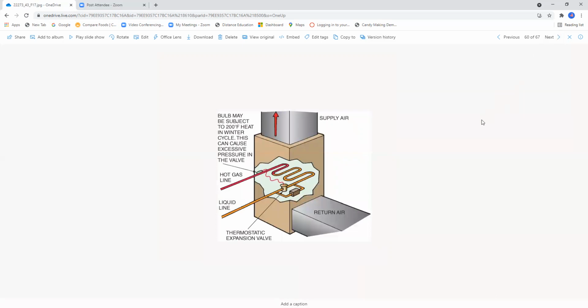Okay, here we have a bulb, and this is something we haven't really talked about. Let me find the illustration in the book, make sure that we get the correct information regarding this. Okay, this is going to be found on page 1282, under figure 43.17. This illustration shows that care must be taken in the choice of a TXV. If an ordinary TXV sensing bulb were to be mounted on this gas line, it would get hot enough to rupture the valve diaphragm. So be careful where the TXV sensing bulb goes. The manufacturer will tell you where it goes. Don't put it in the wrong position. Otherwise, you could actually rupture the power head here. Not a good idea.